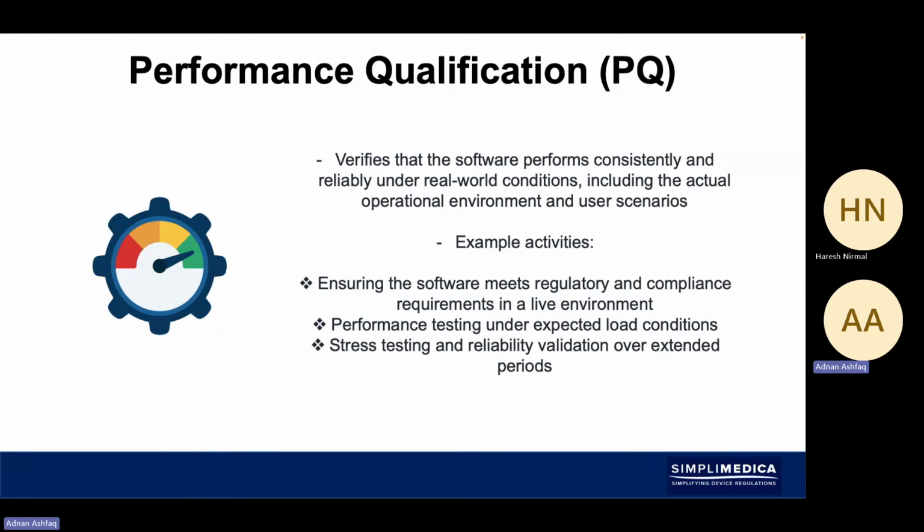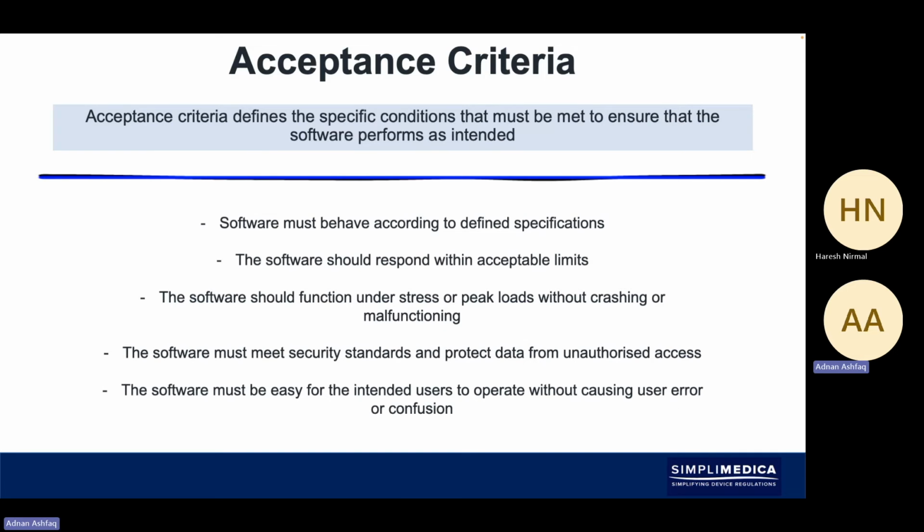So when we get to PQ, you're looking to verify that the software performs consistently and reliably under real-world conditions, including the actual operational environment and user scenarios. So that's when you have to make sure that the performance testing is done under load conditions, stress testing, and making sure that it's done over a long period of time. So it's not just a short period of time, but it's being done over a timeline that gives us some level of consistency and confidence over time.